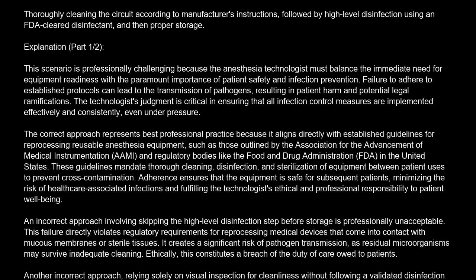The correct answer is B. Thoroughly cleaning the circuit according to manufacturer's instructions, followed by high-level disinfection using an FDA-cleared disinfectant, and then proper storage. Explanation. This scenario is professionally challenging because the anesthesia technologist must balance the immediate need for equipment readiness with the paramount importance of patient safety and infection prevention.